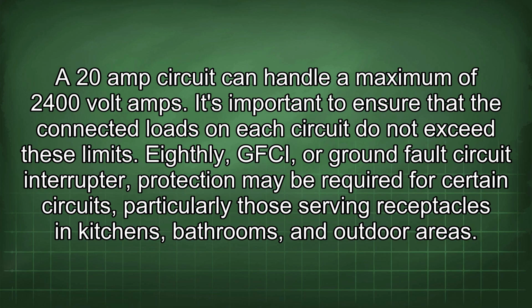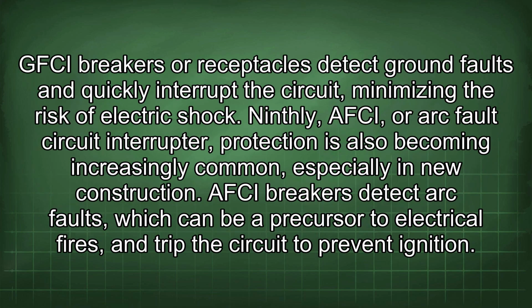Eighthly, GFCI, or ground fault circuit interrupter, protection may be required for certain circuits, particularly those serving receptacles in kitchens, bathrooms, and outdoor areas. GFCI breakers or receptacles detect ground faults and quickly interrupt the circuit, minimizing the risk of electric shock. Ninthly, AFCI, or arc fault circuit interrupter, protection is also becoming increasingly common, especially in new construction. AFCI breakers detect arc faults, which can be a precursor to electrical fires, and trip the circuit to prevent ignition.